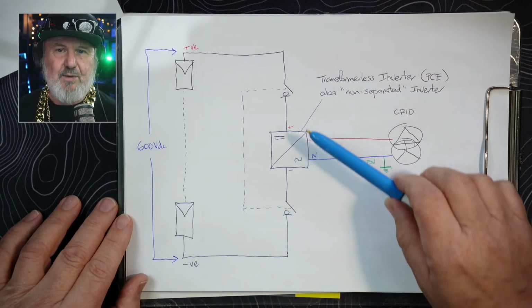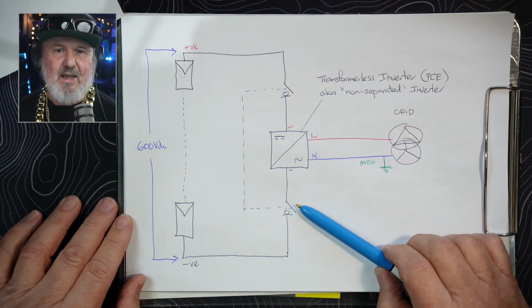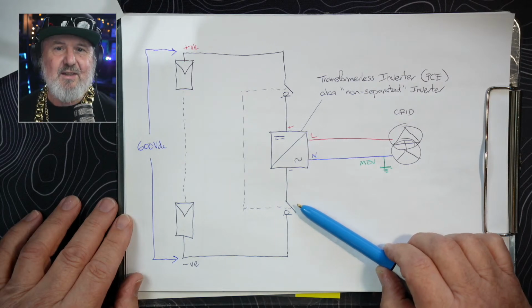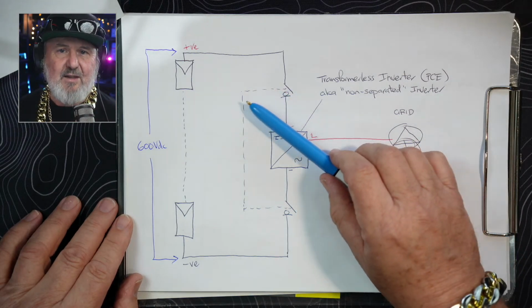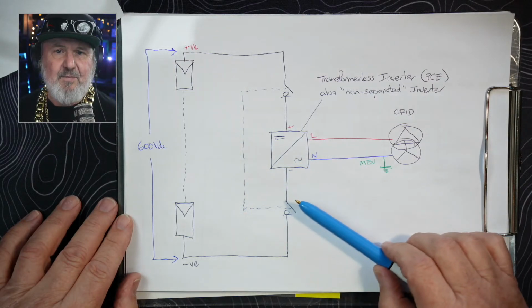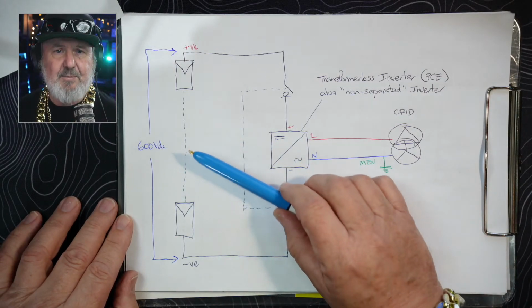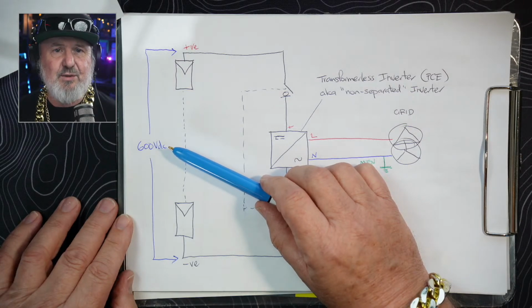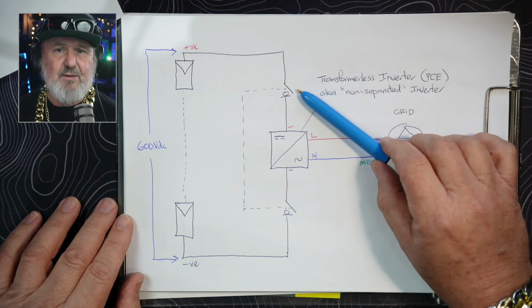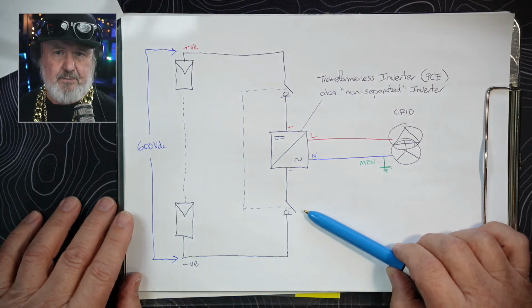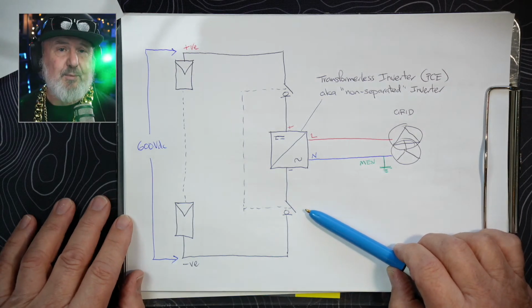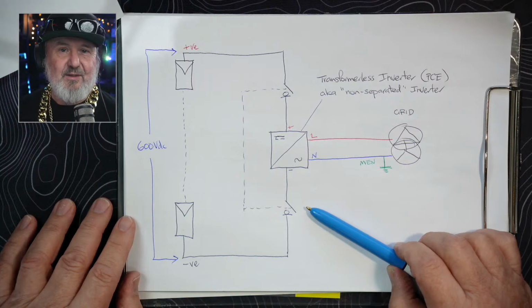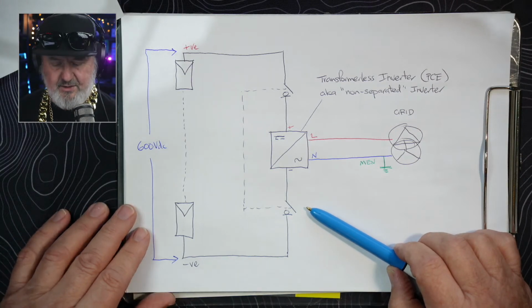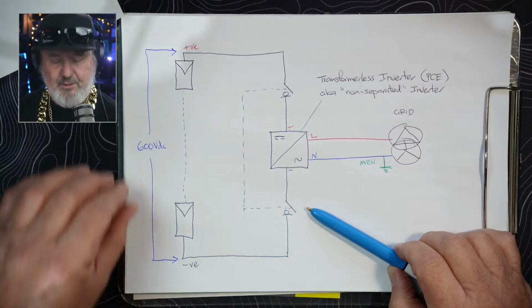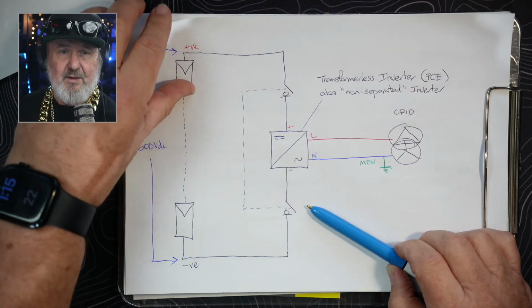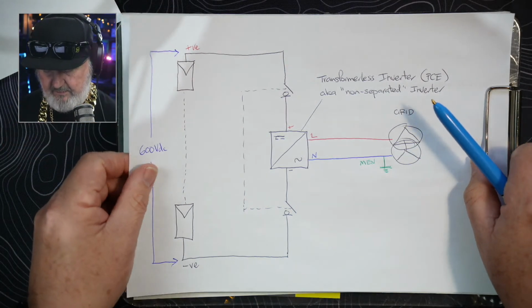Now, you might think that we've still got those two switches there and they're in series, and therefore when we operate them, because they're ganged, the dotted line indicates that they're ganged, that we would be interrupting the 600 volts in two 300 volt sections. So 300 volts here and 300 volts here. That is true under normal operation, but these have got to work under fault conditions, and fault conditions make this all a bit messy. So let me bring a fault condition in.